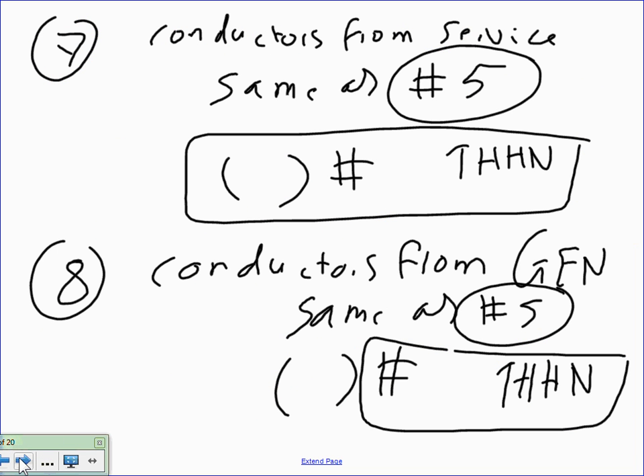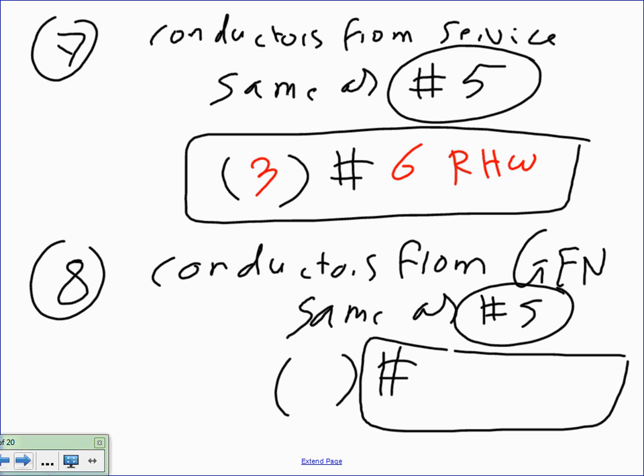Step number 7, conductor from the service. If you can see, guys, I said same as number 5. And what was number 5? 3 conductors, number 6, RHW insulation. And the same for number 8. Number 8 is also the same as number 5 calculation. 3 conductors, RHW, and that's why Chris said they're the same. Chad, why are you bothering us? Bothering you guys because you are in the business of sizing. These could be different as we move on. So 7, 8, and 5 are identical. Any question, guys, about this? Sizing it?